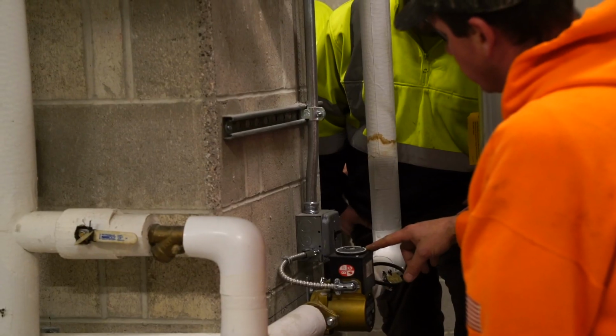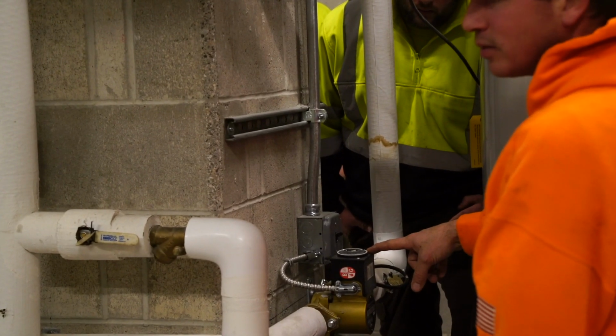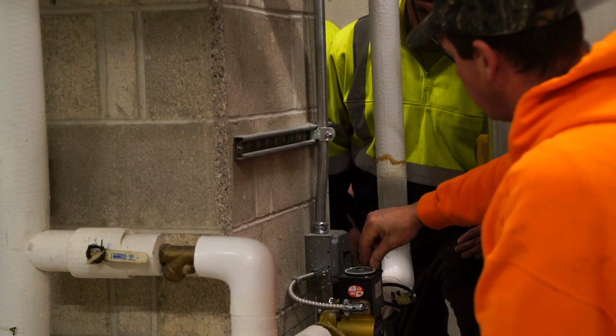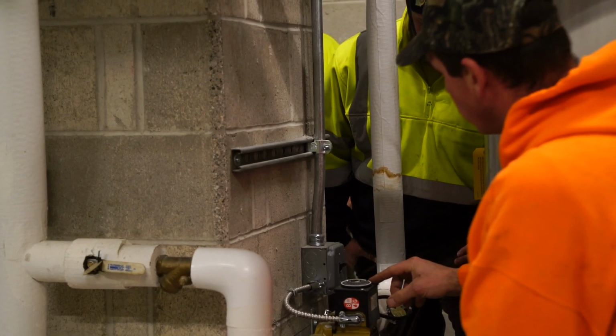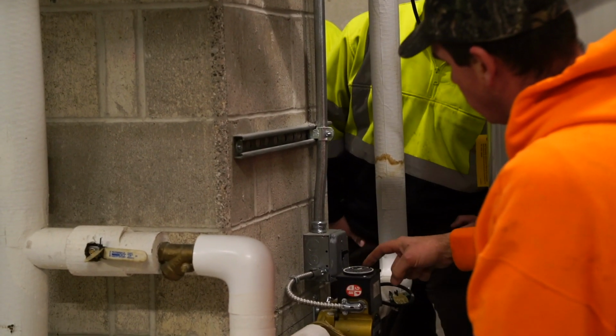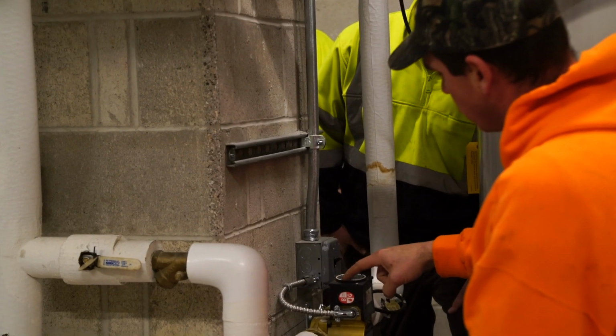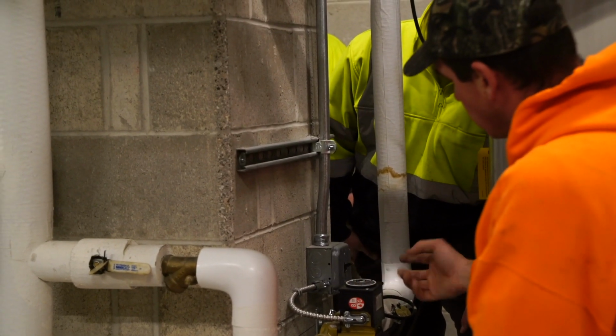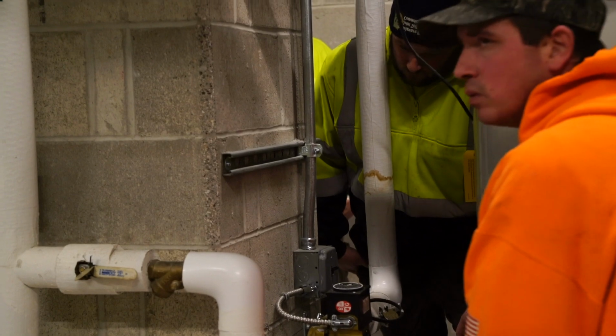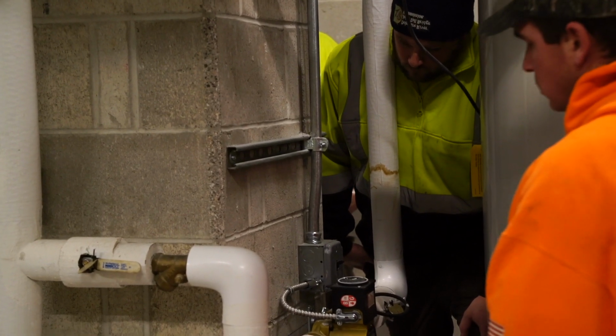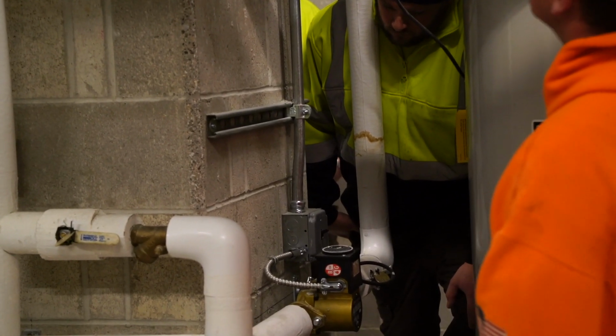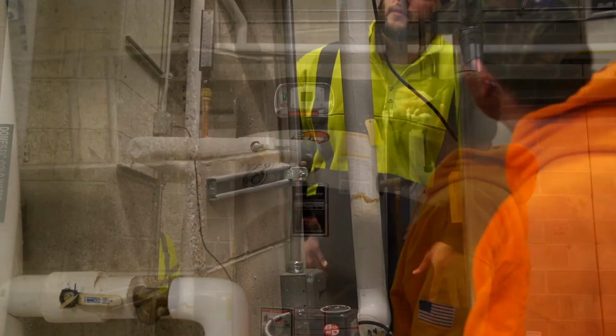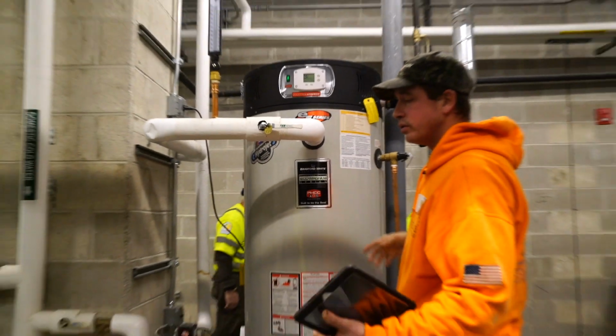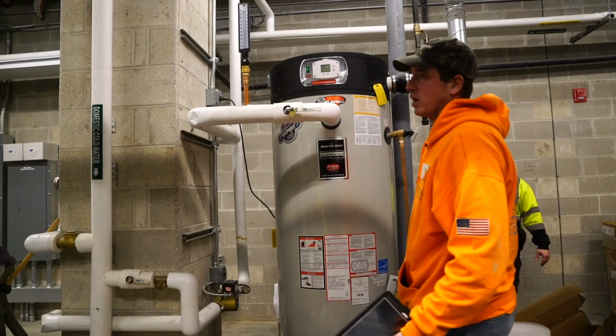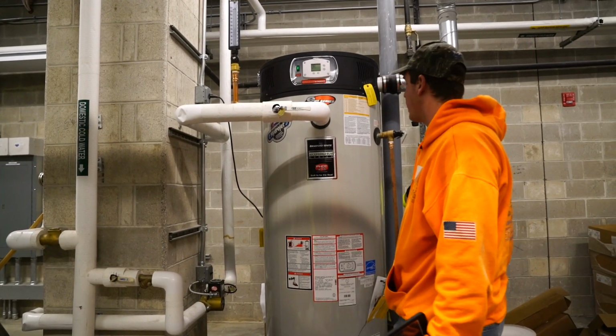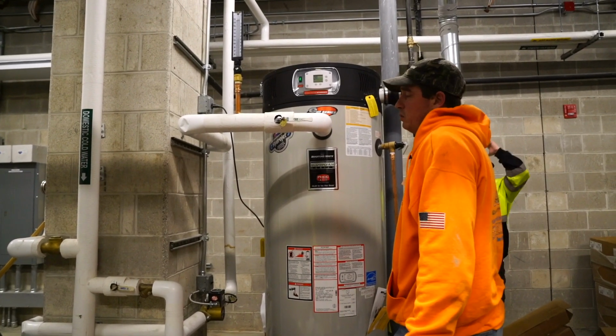The little switches here, it's basically like a Christmas light timer. If you just close a couple of them, it'll decrease the time. These ones that are closed here, that's when it's off. All these ones that are open here, it's open from, like I said, 5 to 11, constantly recirculating. You do have your switch to shut it off. If power ever goes out, all automatic. It turns itself back on, it lights itself. You don't have to ever light any pilots, anything like that. Everything is done on its own.